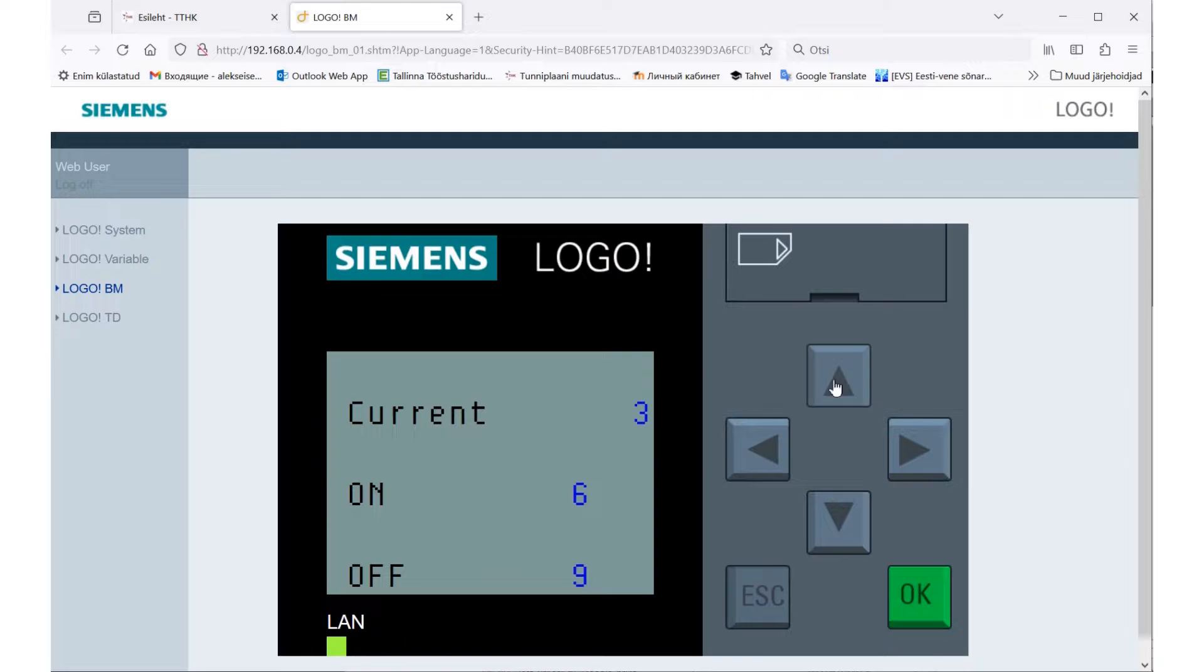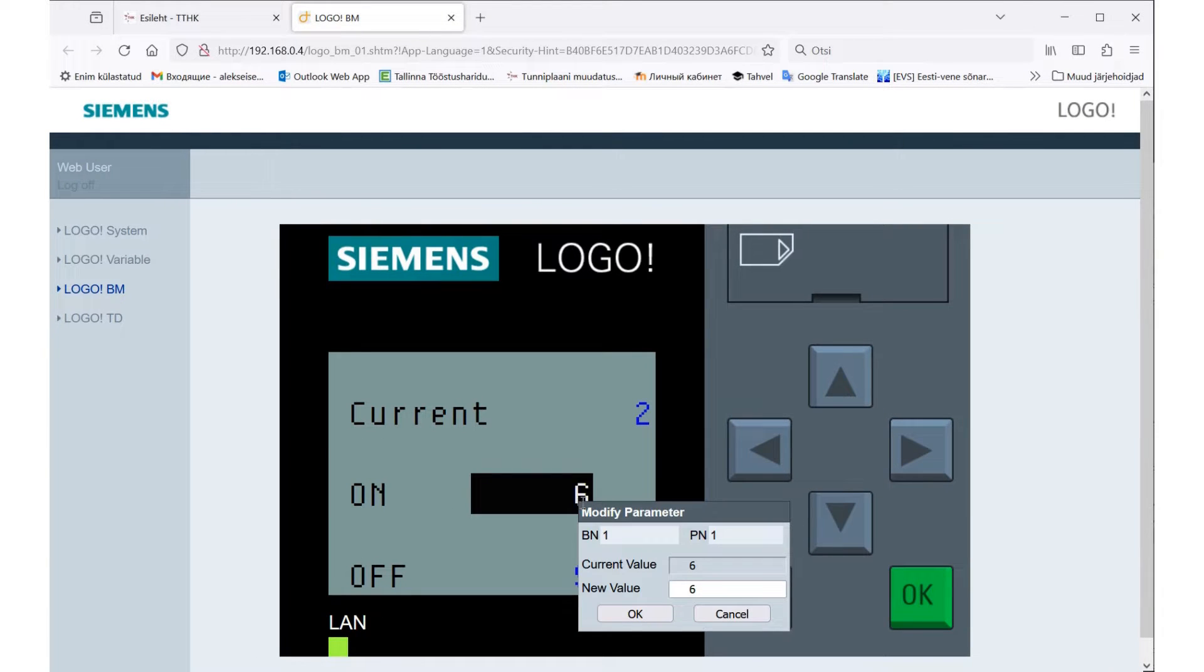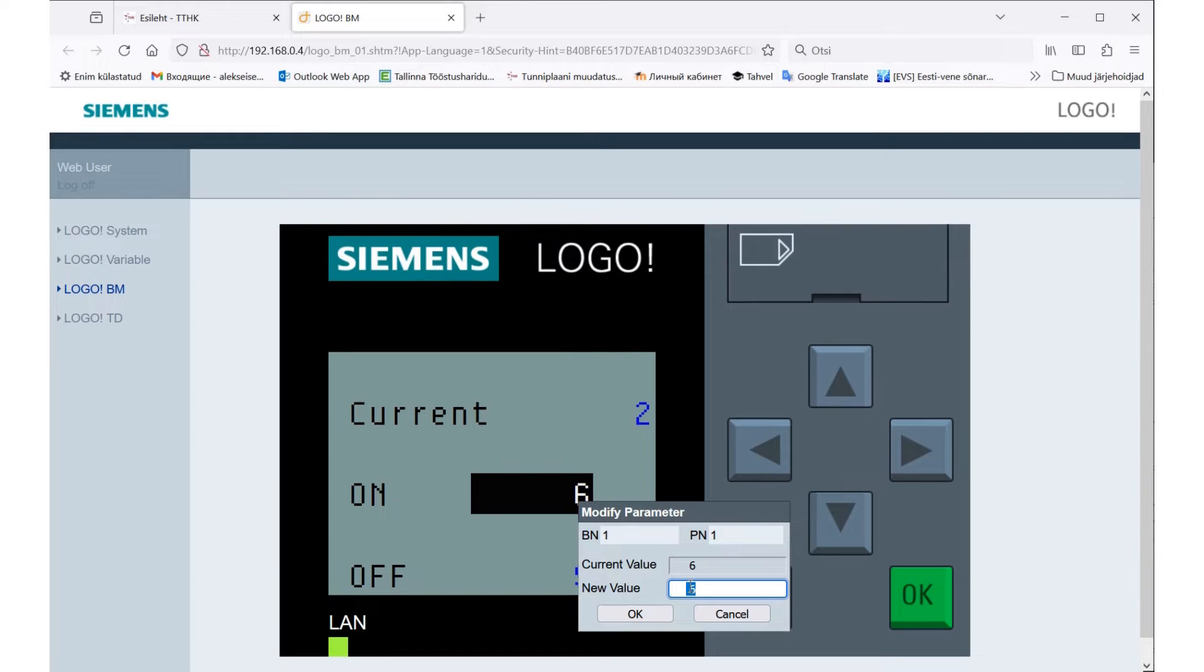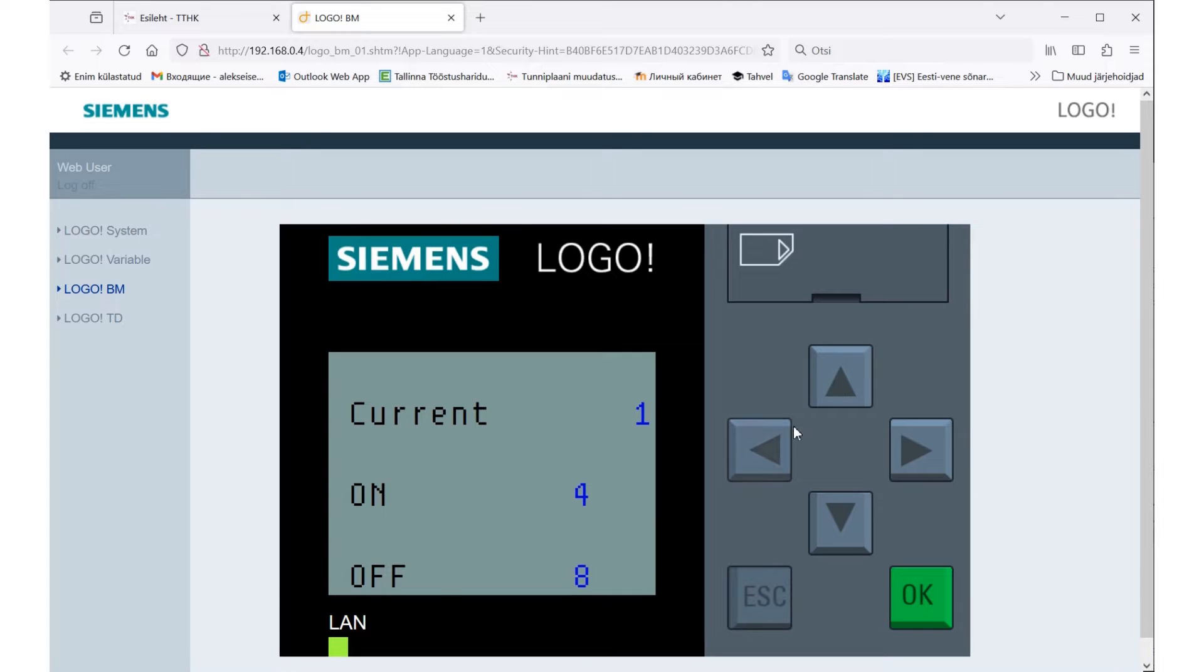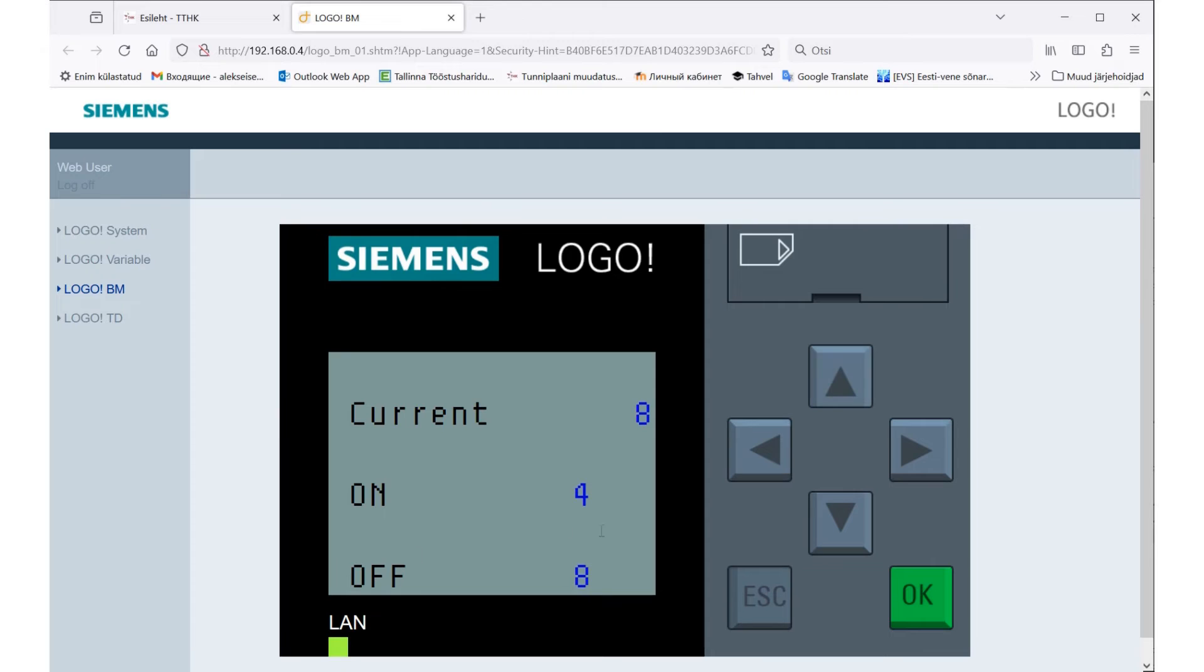Let's try changing the parameters of the key on counter. So select the ON parameter and enter a new value, let it be four. Turn on the cursors. Press the cursor up key up. Three, four - the light comes on. Five, six, seven, eight - the light turned off. Now the counter is counting up.